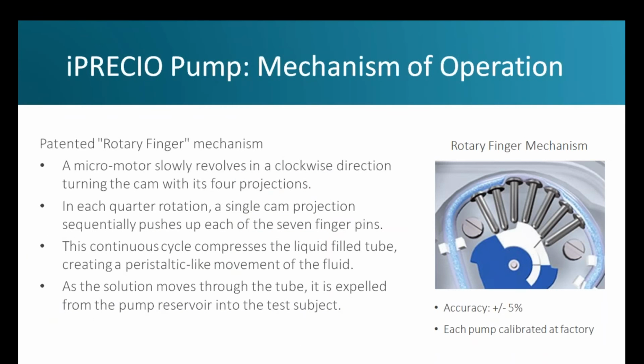So let's go over how the iPRECIO pump works to administer solutions as programmed. The technology driving the infusion is a patented rotary finger method. This method is a unique form of peristalsis. Once the pump is activated, a micromotor slowly revolves in a clockwise direction, turning the cam with its four projections. In each quarter rotation, a single cam projection sequentially pushes up each of the 7 finger pins. This continuous cycle compresses the liquid-filled catheter, creating a peristaltic-like movement of the fluid. As the solution moves through the tube, it is expelled from the pump reservoir into the animal. This unique method provides accuracy better than plus or minus 5%. And for additional confidence, each pump is tested and calibrated at the factory to ensure that every pump works properly.